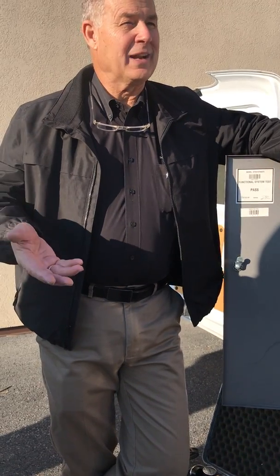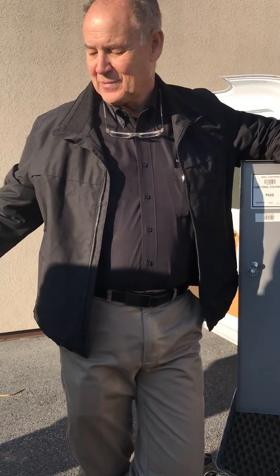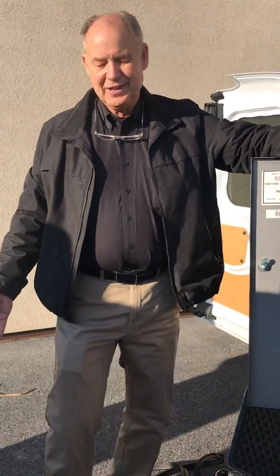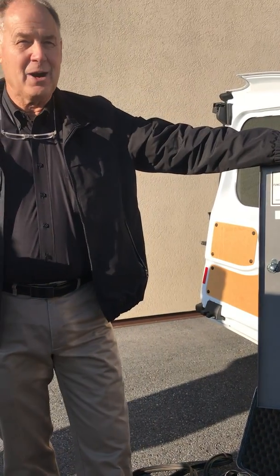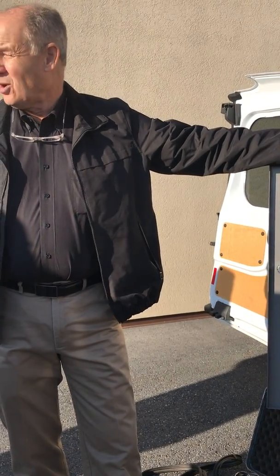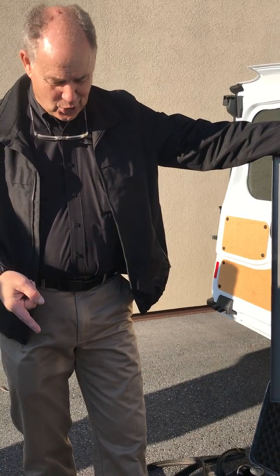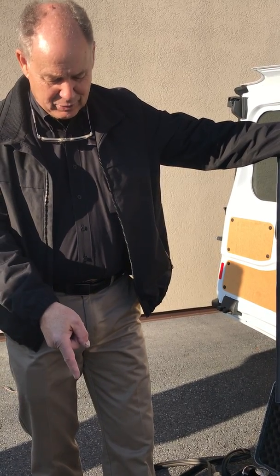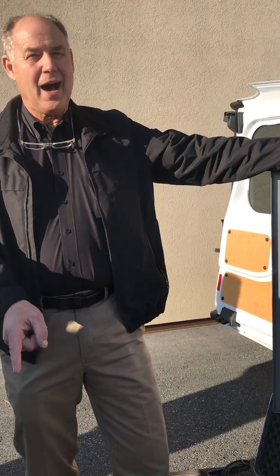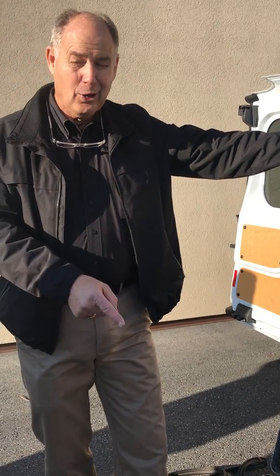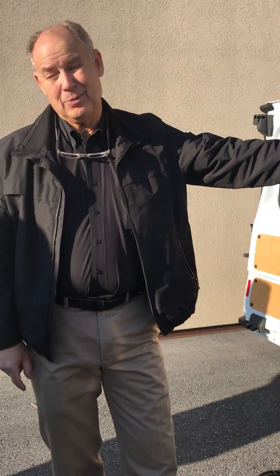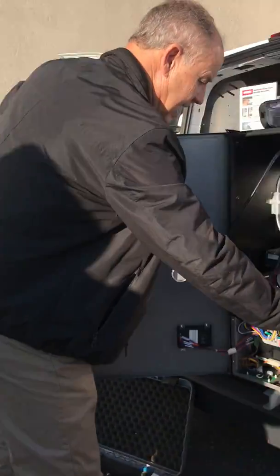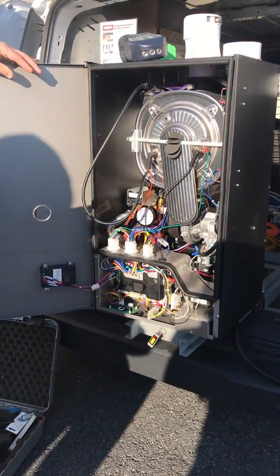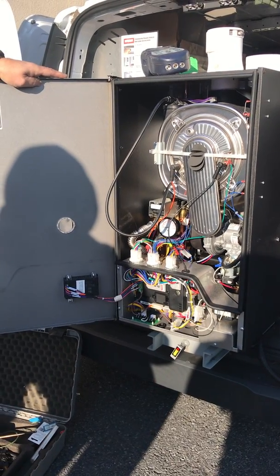So the only reason I know, I was on a job doing training and they had a cord, and I said, look, it's I and O. One of them's on, one of them's off. I looked at the cord and it was powered on and pushed to the I. So I is on, O is off. I'm just letting you know. I've actually gone to jobs that worked, and when I went to check it out, I ended up bumping that little switch and I shut it off. And then you don't get the gas valve to light.